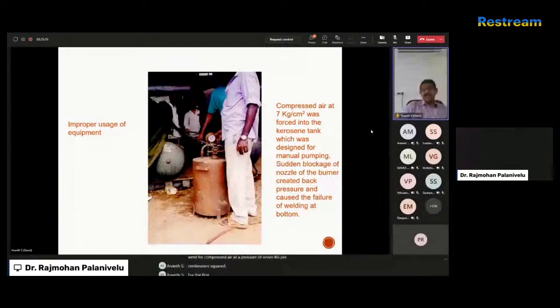So there was a forced kerosene system, where instead of manual pumping, they were getting it pumped. But on a fateful day, there was a sudden blockage of the nozzle on the burner end, which created a back pressure. Because of this back pressure, the fillet weld at the bottom of the small tank, which could only withstand 4 kg per centimeter square, failed when 7 kg per centimeter square was introduced at the backflow pressure. It opened at the bottom, and the kerosene entered the air at high pressure, creating a huge vapor cloud.